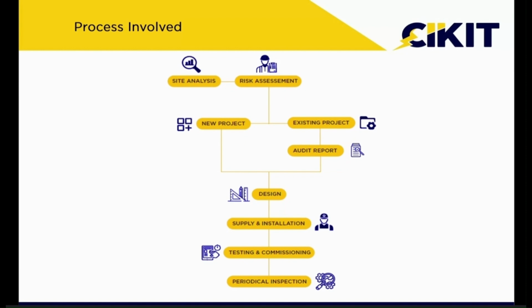The second step is performing risk assessment calculations. We cannot say that all buildings require a lightning protection system; it is not mandatory for all structures. So before performing the design, the first thing is to decide whether lightning protection is required for this particular site or not. If it is required, only then do we proceed to the design. If the lightning protection system itself is not required, there is no need to go for the design. That decision will be made on the risk assessment only. Based on the output of the risk assessment, we perform the design, then material supply, then installation.